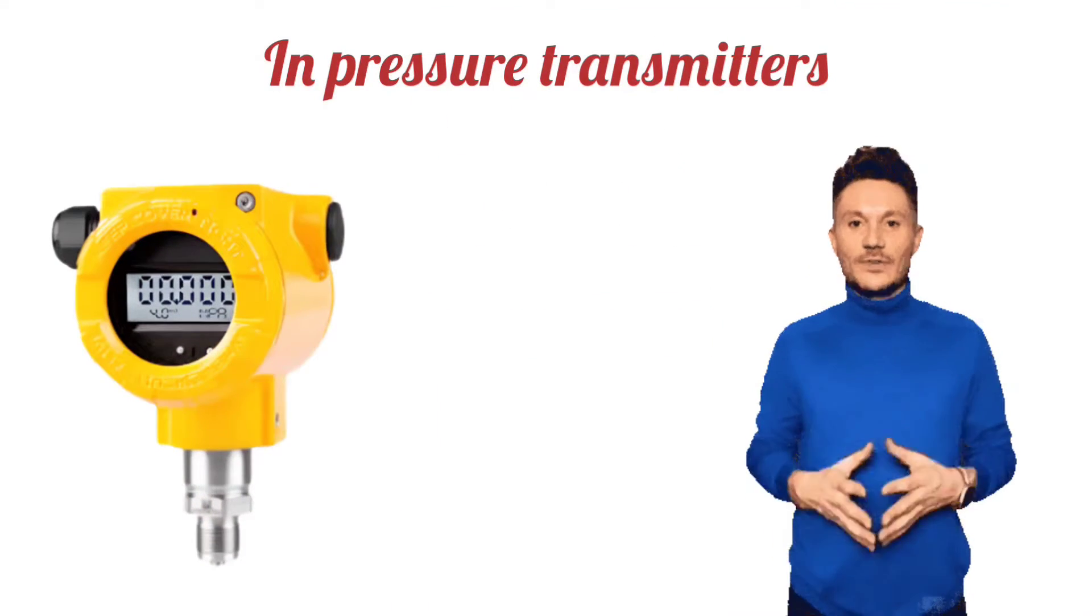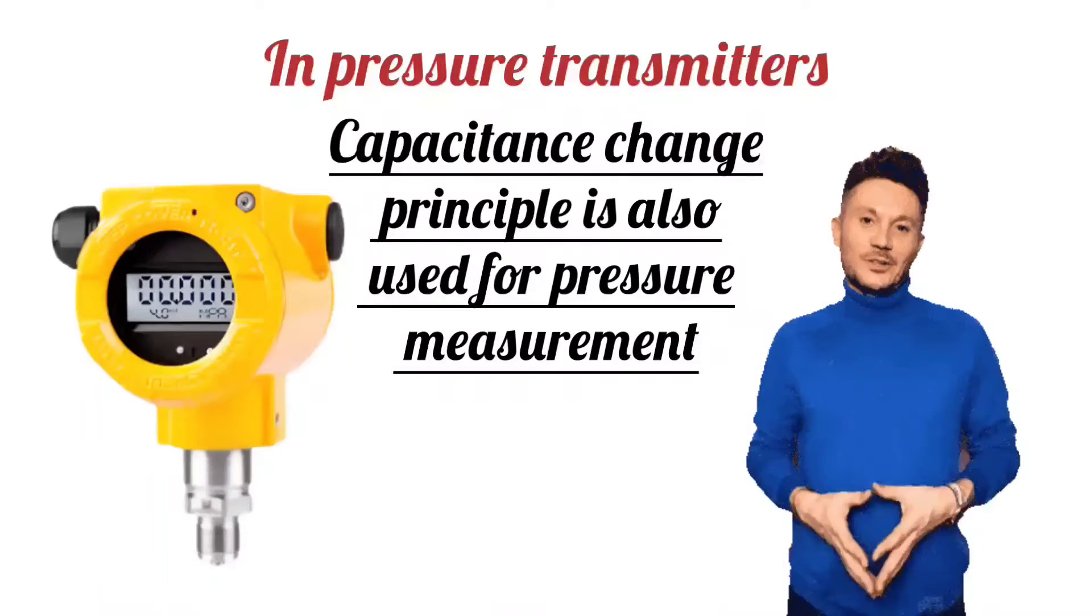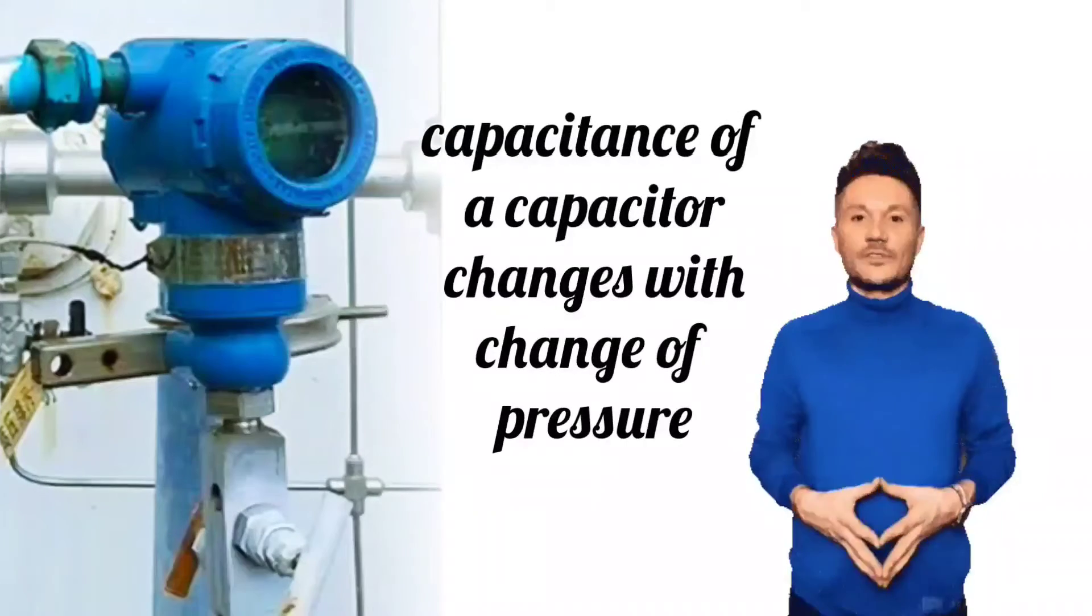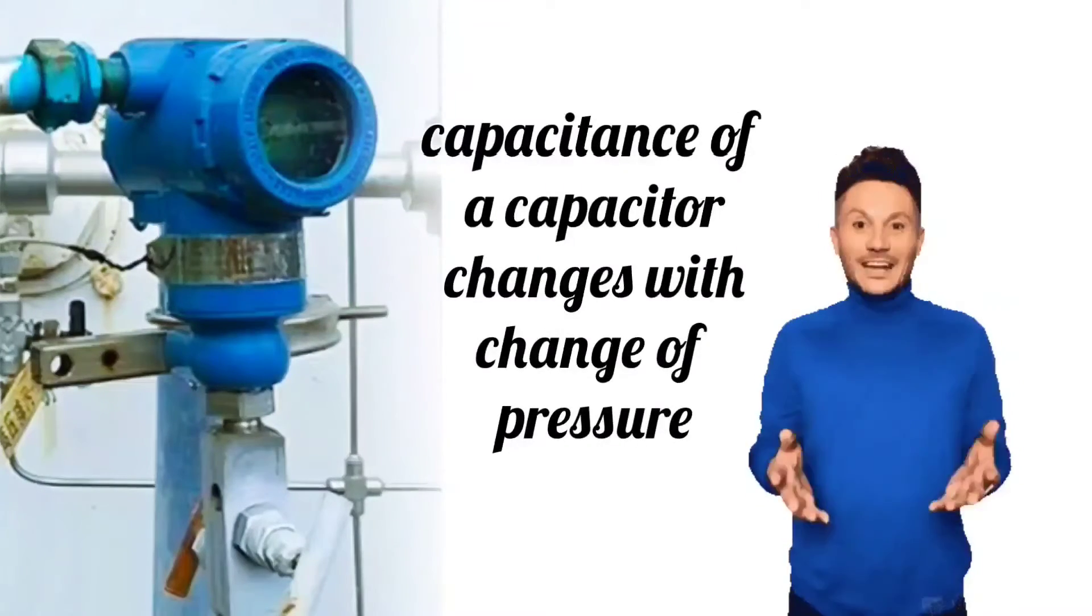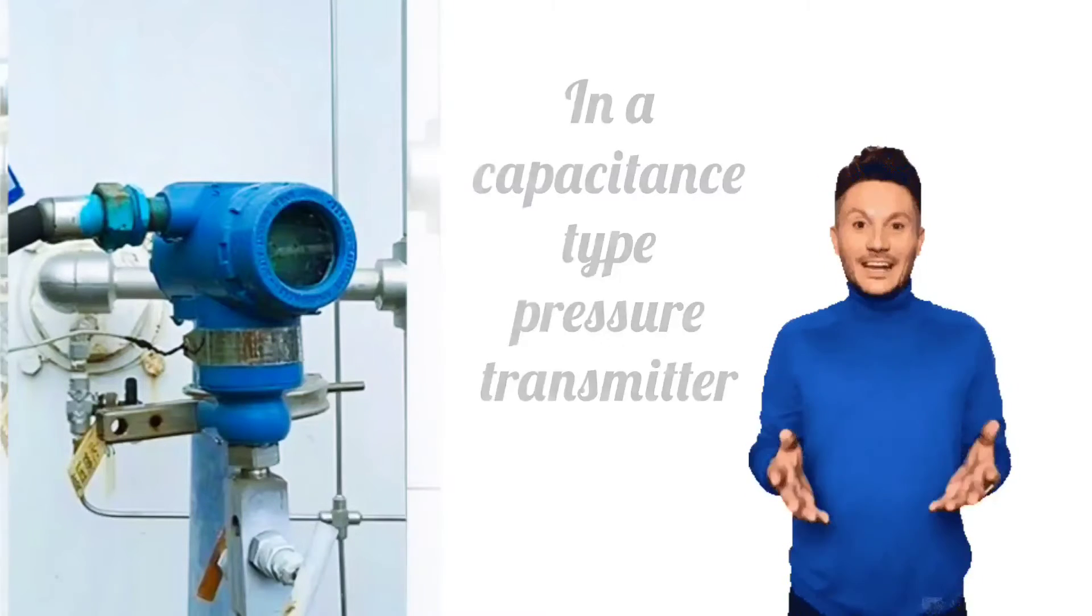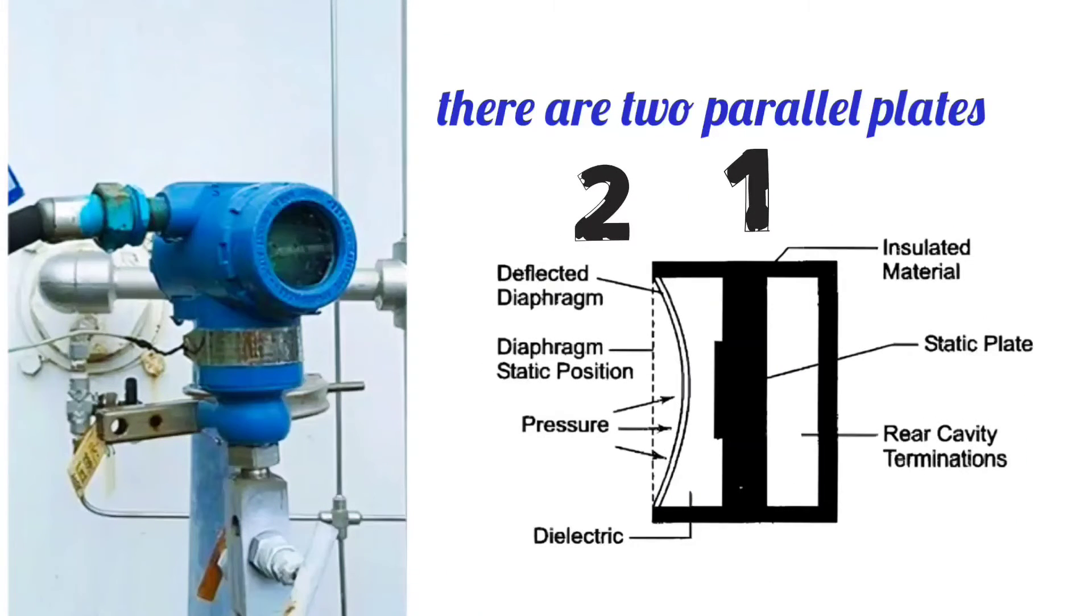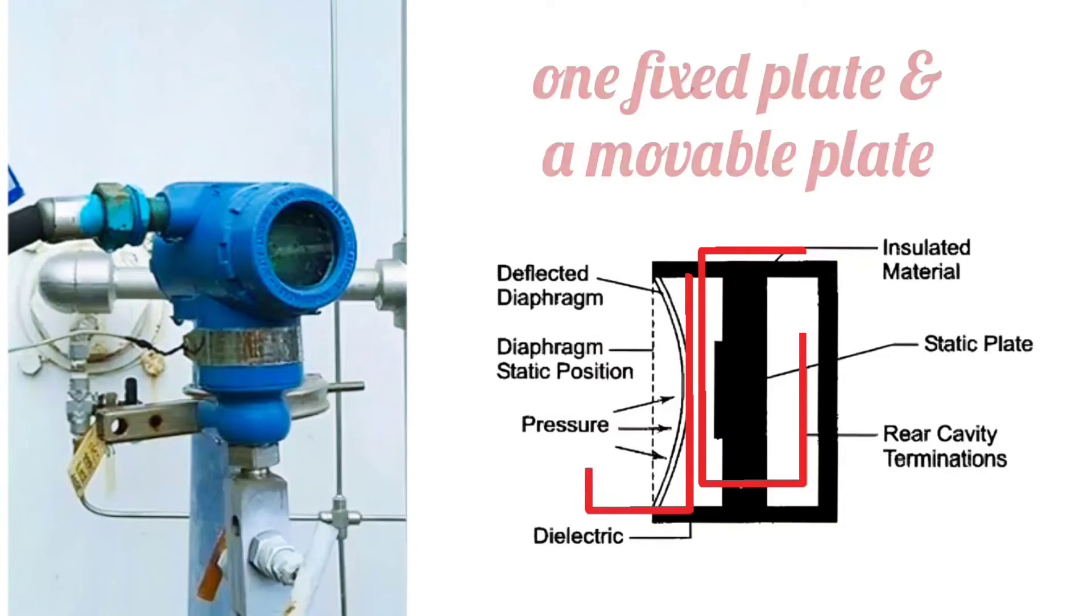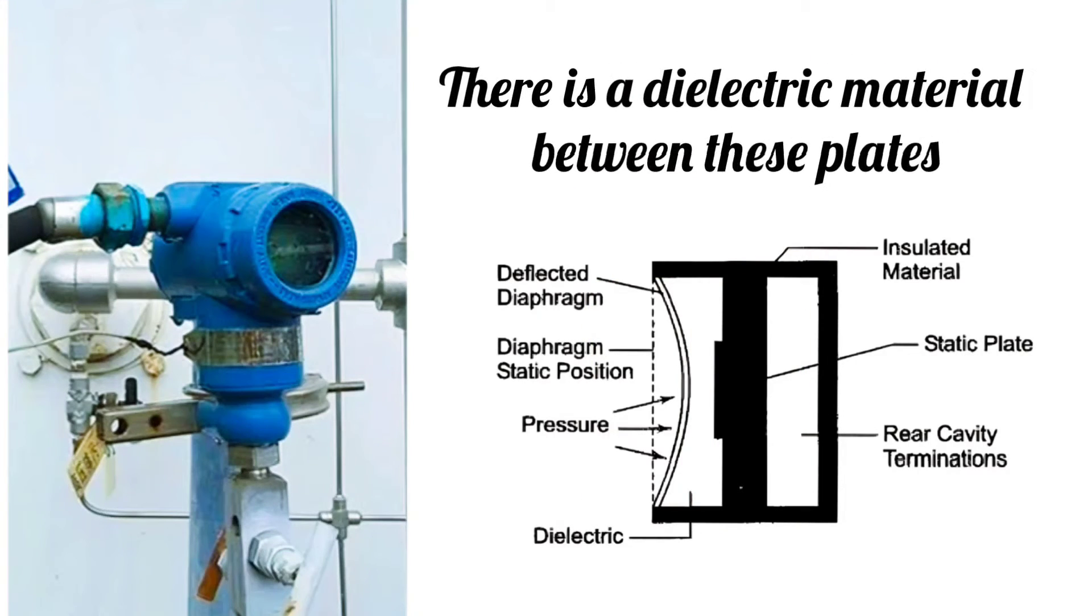In pressure transmitters, capacitance change principle is also used for pressure measurement. In this principle, the capacitance of a capacitor changes with the change of pressure. In a capacitance type pressure transmitter, there are two parallel plates - one fixed plate and one movable plate. There is a dielectric material filled between these plates.